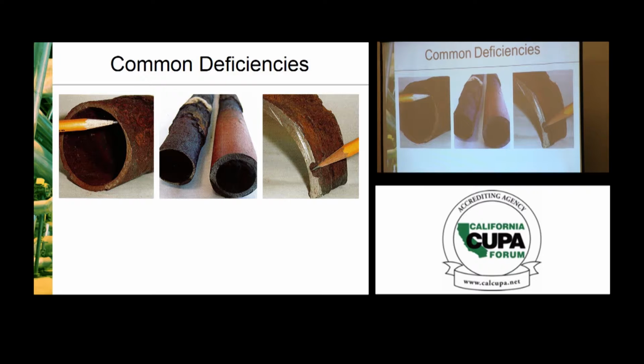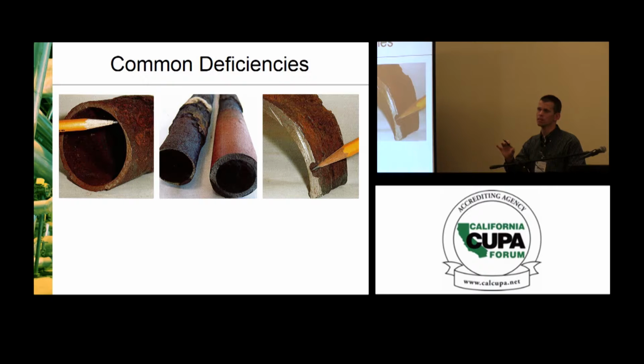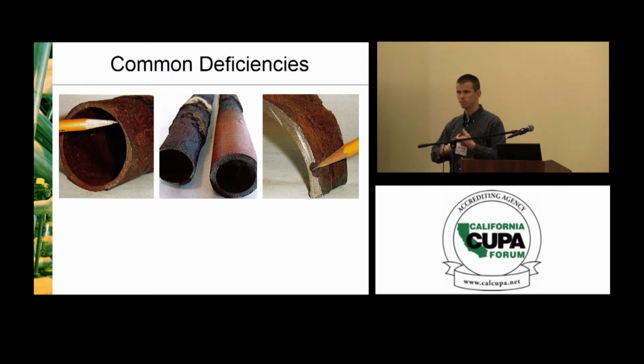when it comes to insulated pipe and doing mechanical integrity inspections, we recommend doing a thorough visual inspection of all pipes. So before you ever get into measuring wall thicknesses, pits, ultrasonic testing, x-ray, whatever it may be, a thorough visual inspection. Use your eyeballs. They're very valuable tools. They work really good, and look at everything. So when it comes to insulation, where you can't see the pipe and all you can see is the insulated surface, hopefully the jacketing. So ammonia insulated pipe should be jacketed, probably either with PVC jacketing or aluminum jacketing.